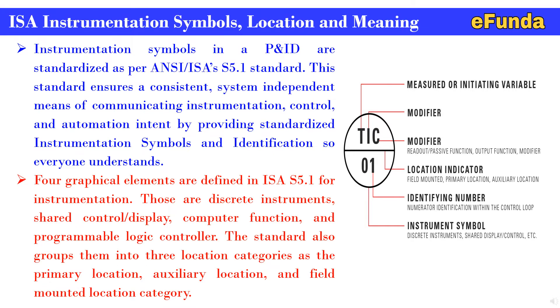Looking at the figure, one can see a circle with a single line at the center and TIC01 indicated. The nomenclature is as follows: the first letter T is the measured or initiating variable; the second letter I is the modifier indicating indication; the third letter C is a modifier for readout, passive function, output function, etc. The center line at the circle is the location indicator. The number 01 is the identifying number — the loop identification within the control loop. The circle represents the instrument symbol for a discrete instrument, shared display, or control.